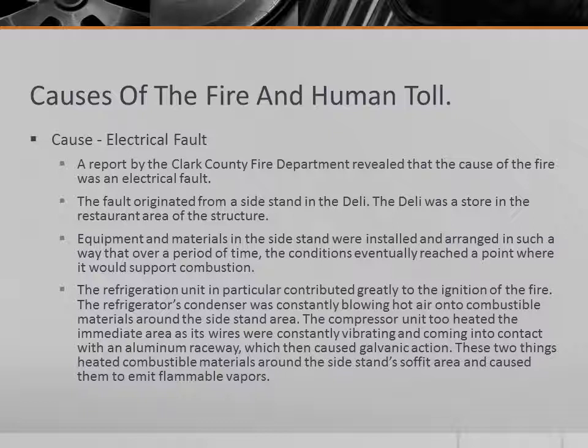Equipment and materials in the side stand were installed and arranged in such a way that over a period of time the conditions eventually reached a point where it would support combustion. The refrigeration unit, in particular, contributed greatly to the ignition of the fire. The refrigerator's condenser was constantly blowing hot air onto combustible materials around the side stand area. The compressor unit, too, heated the immediate area as its wires were constantly vibrating and coming into contact with an aluminum raceway, which then caused galvanic action.